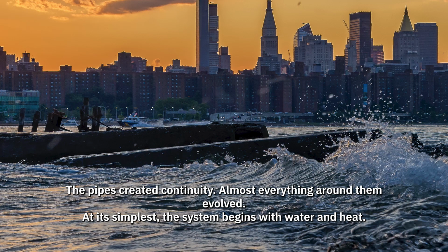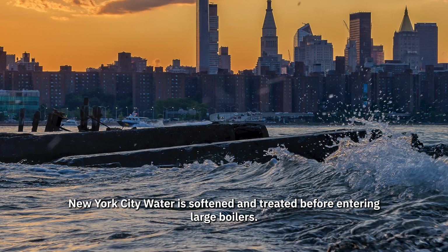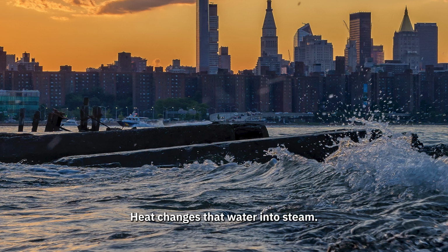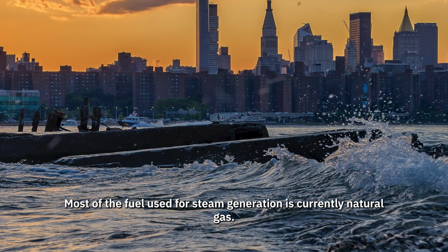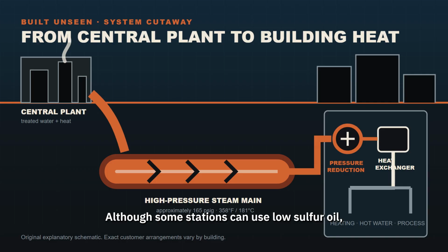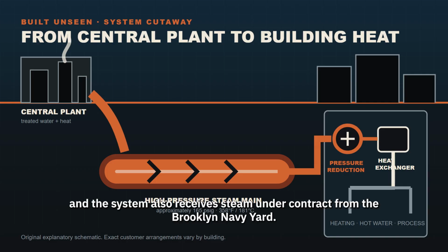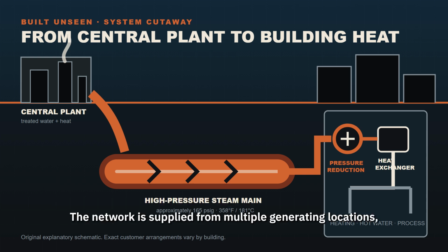At its simplest, the system begins with water and heat. New York City water is softened and treated before entering large boilers. Heat changes that water into steam. Most of the fuel used for steam generation is currently natural gas, although some stations can use low-sulfur oil, and the system also receives steam under contract from the Brooklyn Navy Yard. The network is supplied from multiple generating locations rather than one irreplaceable boiler room.